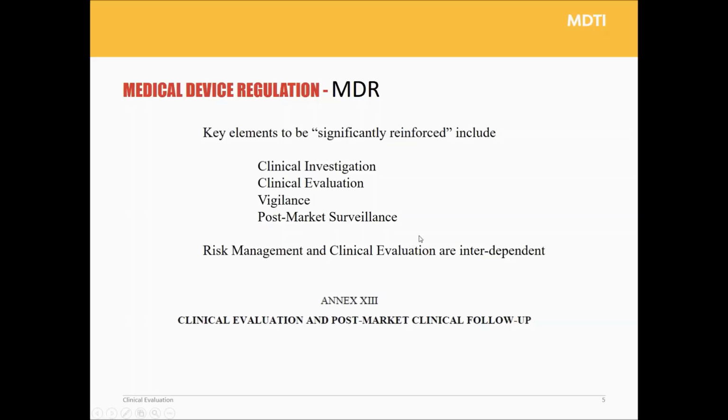And these ones, vigilance and PMS, are not always automatically considered in terms of clinical evaluation, but now they're very, very much dovetailed with them. Additionally, risk management and clinical evaluation are now interdependent. So your clinical evaluation must include assessment of risk, and your risk must include assessment of the clinical safety and performance.